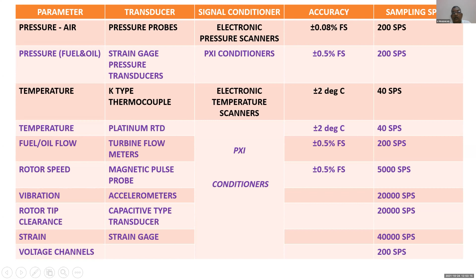The rotor tip clearance, which measures the tip clearances between the running rotors and the casings, is around 0.5 mm, measured at 20 kilo samples. Strain gauges go up to 40 kilo samples, and the normal voltage channels around 200 samples. So the whole data acquisition system was developed to take care of these many parameters for these desired accuracies and for these desired sampling speeds.